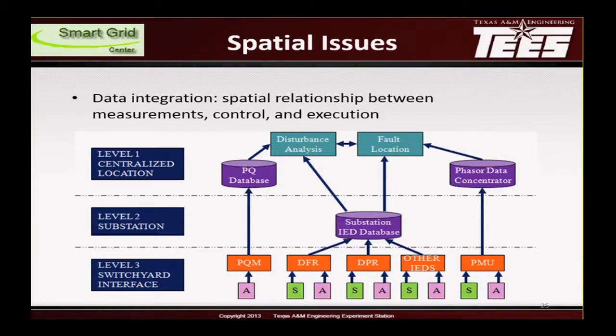So for example, if I'm using SCADA - supervisory control and data acquisition - and I'm worried about the topology processor of the state estimator, or the front-end state estimator, if I use data from relays and recorders, I can actually verify exactly whether the topology is as it should be.